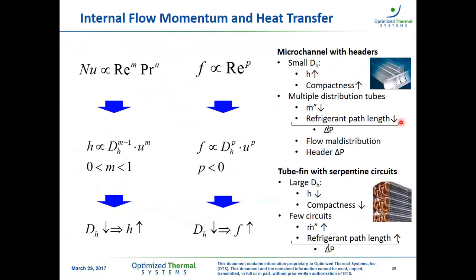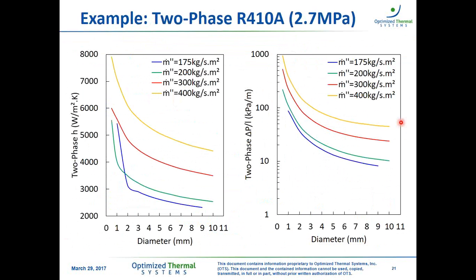On the other hand, the conventional tube fin heat exchangers have larger diameters, and they have reduced heat transfer coefficient, less compactness, and potentially the number of circuits may increase the mass flux and the overall refrigerant path length that may affect the pressure drop. So the idea here is that if we reduce the tube diameter, we may get the benefits from both concepts altogether. Now let's look at some numbers.